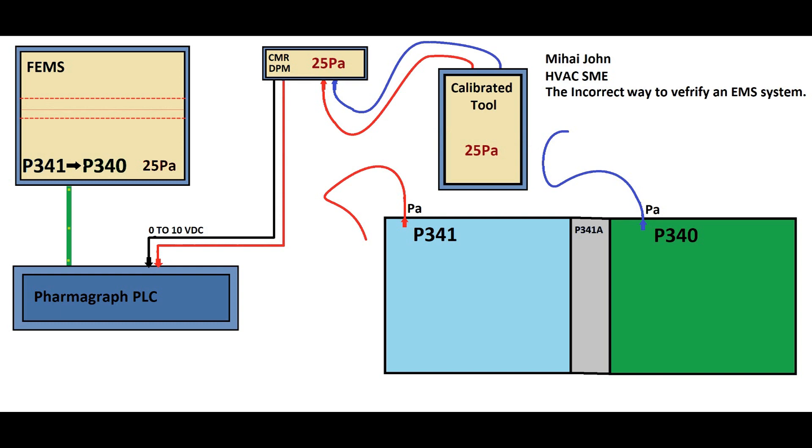Calibration specifically focuses on confirming the accuracy of the DPM and its data interpretation within the PharmaGraph software. The process involves aligning the displayed value of the front-end panel with those of the calibrated tool. This validation step ensures that the DPM accurately measures differential pressure and transmits correct data to the PharmaGraph software.